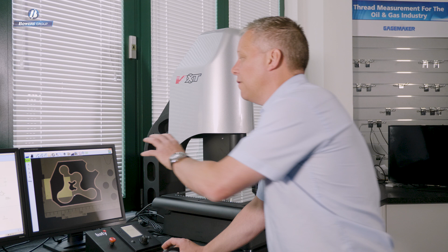So this is the view that we're used to seeing on a 500mm screen profile projector, and now for the first time we can actually replicate that on a camera-based vision system. So now we have a visual graphical display showing our points, our scanned data points as green and in tolerance. We also have a visual overlay of the DXF placed over the top of the stitched image. So anything, even if we haven't measured the feature, we can still see where it appears in relation to the DXF. But the final thing that a software-based system like this can give you is an actual result. If we want to, we can dimension that profile and actually put a number on it. And that's the massive difference between this subjective view that you have to take with a profile projector and using this method where we can automate the process.